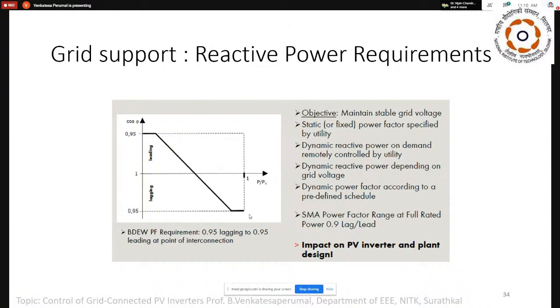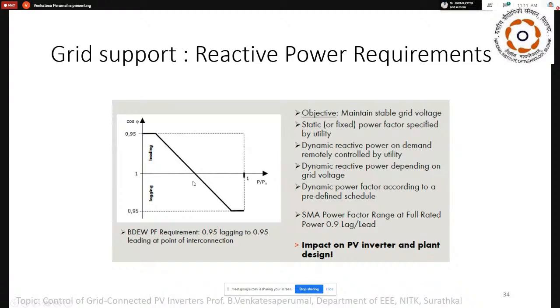But why is it restricted in most grids? People say that if it is a 1 megawatt PV inverter, they can use the full 1 megawatt during the night time. That is not possible, because the DC bus capacitor value is not going to support the reactive power completely. People normally think that a 1 megawatt grid-tie inverter will support 1 megawatt of reactive power at night, but that is not possible because the DC bus capacitor requirement completely changes. So at present, most people give a reactive power variation from 0 to 0.95 power factor, leading and lagging.